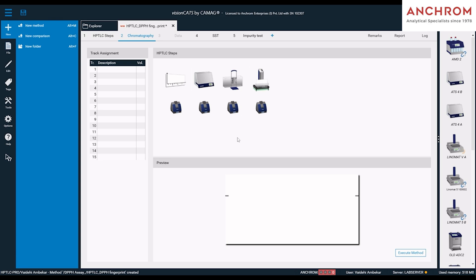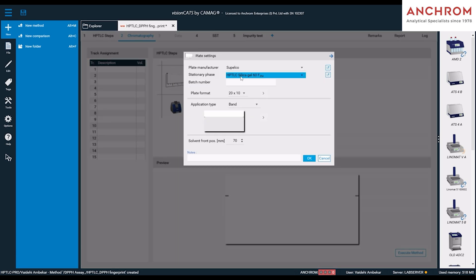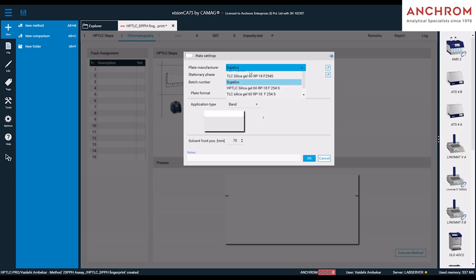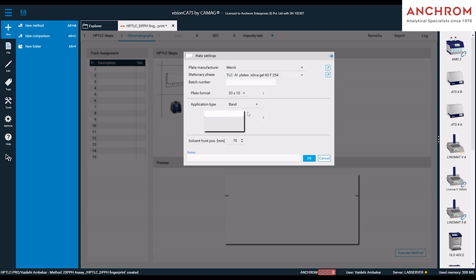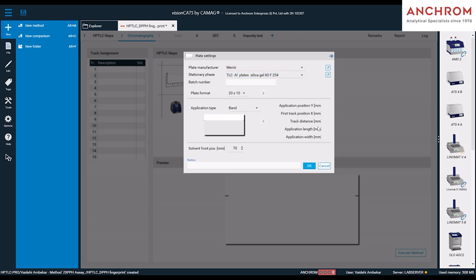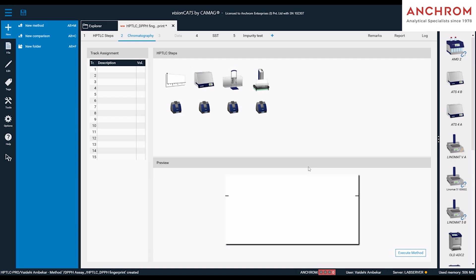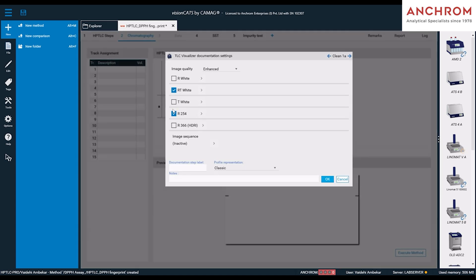Under Chromatography, click on the Plate Image, i.e., Plate Layout, to add the stationary phase details required for the analysis as shown here. Select the plate detail name, plate format, application details, solvent front as per the requirement of the analysis. Click OK after completion. Now, click on the Visualizer 2 icon and select the illuminations in which you need to capture the blank plate image, that is, clean plate image. Then, click OK.